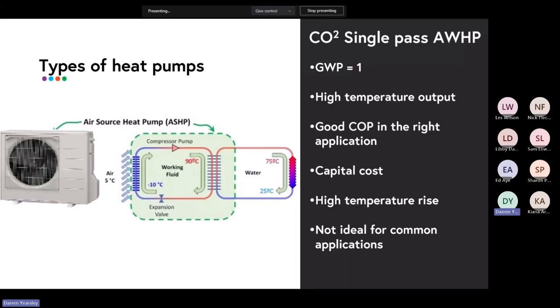Now, when we look at CO2 and single pass, these appliances are very, very efficient during draw-off. Why is that? It's because you have an unlimited supply of 20-degree water coming from the street and filling the system, and your heat pump can operate on that very cold water, and it can heat it up in a single pass. So it can go from 20 degrees up to 70 degrees and then pop it into the top of your buffer. But it doesn't make sense to do all of your energy in that way because the size of the heat pump required to keep up with your instantaneous load is way too big. And so typically you still have a large amount of buffer with a small amount of heat pump.